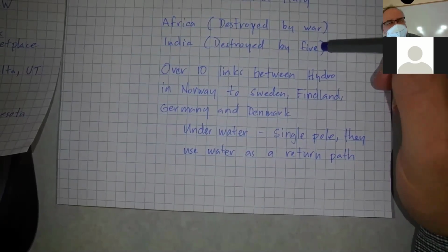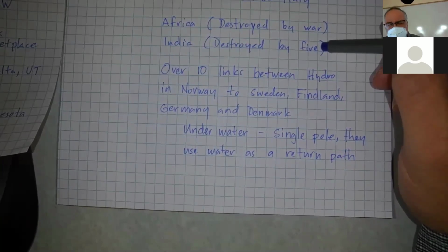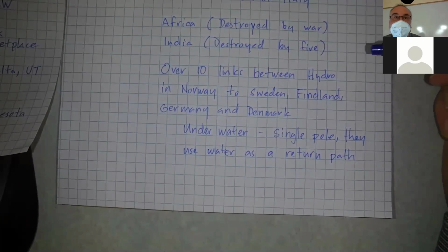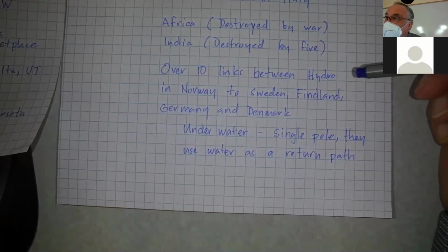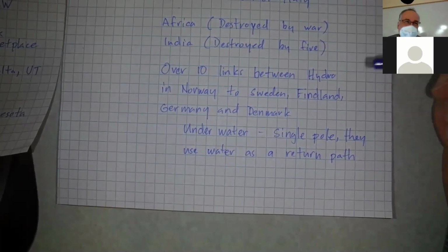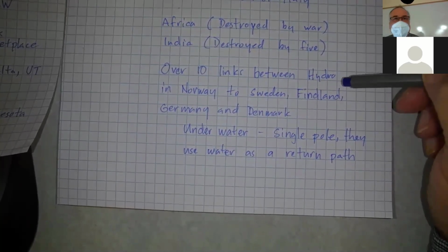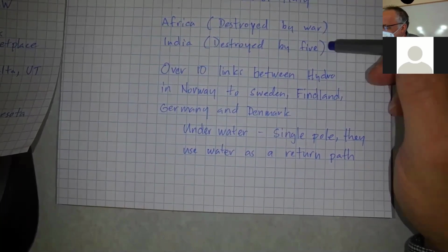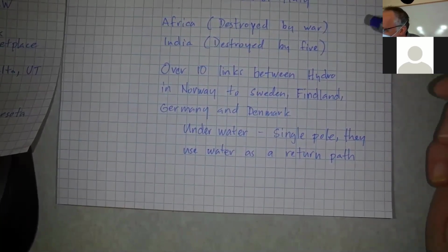They set up the controls such that they didn't want to de-energize the line because they had people knocking on the towers to steal the line for scrap metal. So they kept the line energized. That caused a problem with the valve hall and basically destroyed one of the converter stations.